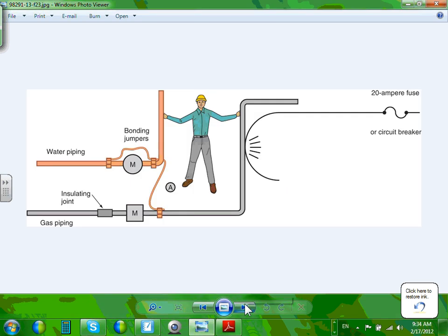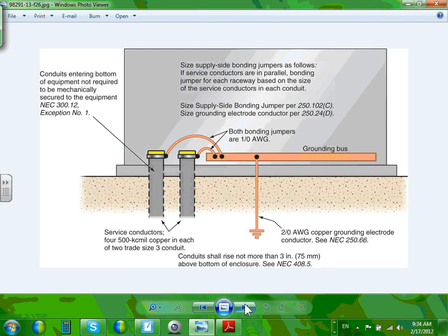Okay, GFCI protection and so forth and bonding. The reason why we bond equipment, guys, is because we don't want things to sit at different voltages. For example, take this. If this has to be bonded through the grid. Why? Because it has electrical wires in it. If it gets hot and Chad grabs into it, and because he's always moving around, grabs it here and grabs the wall, now you got yourself a 100-watt bulb burning.